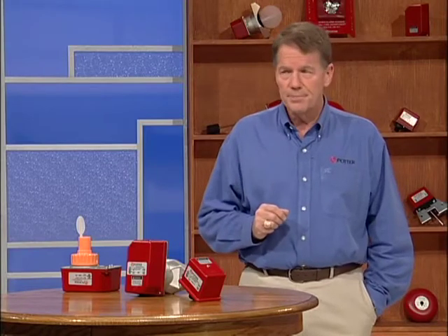However, most sprinkler systems are designed so that once the sprinkler is activated, water continues to flow until the system is shut down. Water flowing for hours through an open sprinkler head or broken pipe can cause major property damage. The purpose of sprinkler monitoring is to watch the sprinkler system for critical changes and then notify the proper authorities.